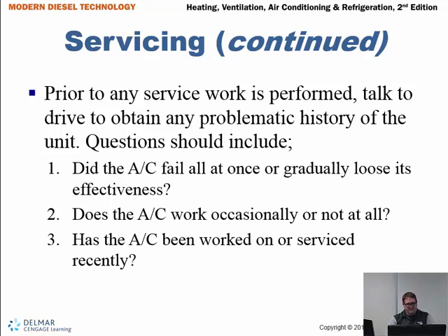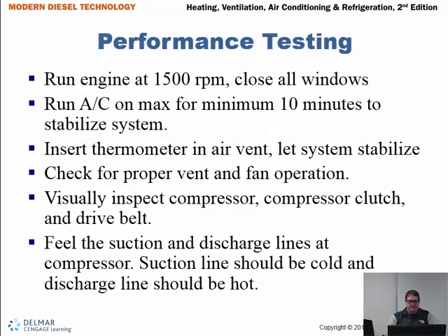obtain any problematic history. The questions that you talk to the customer about should include, did the AC fail all at once, or did it gradually lose its effectiveness over years or seasons? Does the AC work occasionally or not at all? And has AC work been performed on it, or has it been serviced recently?